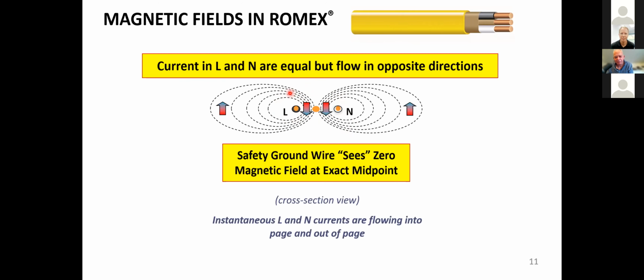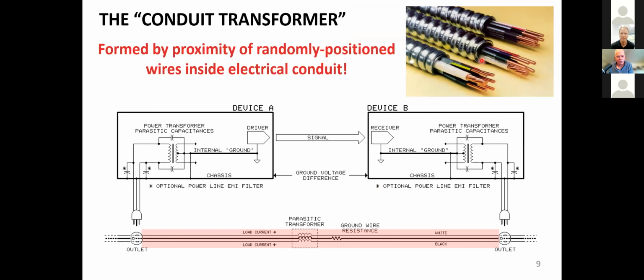But if we go back and look at these wires, the way a commercial circuit, at least in the US, is normally wired, the ground conductor - there's one right there, green with a yellow stripe - has a totally random positioning with respect to the two wires that may be carrying the heavy current in this circuit. So it may be much closer to the neutral conductor than it is to the line conductor, and no cancellation takes place. So we get, as pictured down here, a transformer symbol. It's basically a single turn transformer where the turn is whatever distance we want to consider, say between outlets.